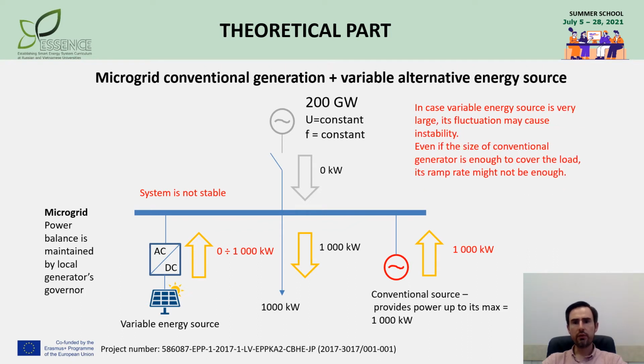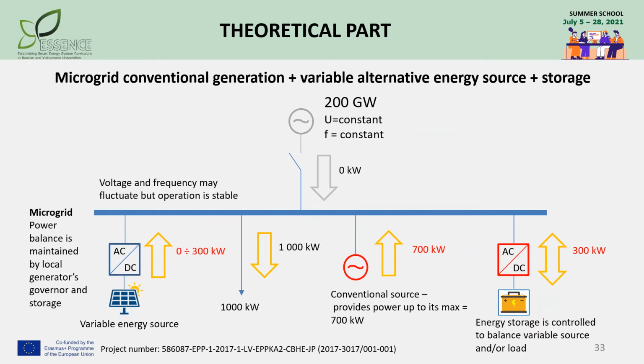Even if the size of the conventional generator is adequate to cover imbalance caused by the variable renewable source, its speed of change of output power might not be enough to compensate sudden imbalance. As a result, the system loses frequency stability. A stable solution can be achieved if energy storage is added to the microgrid. This allows increasing the share of variable renewable sources, compensating real power fluctuations, and increasing system efficiency in general. However, a detailed feasibility study is usually required to define the best combination of sources and their sizes, since a trade-off between reliability and economy always exists.